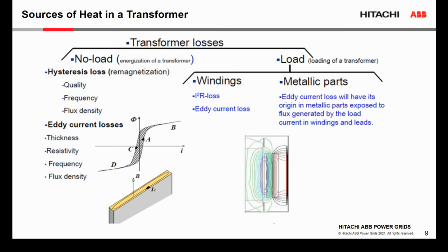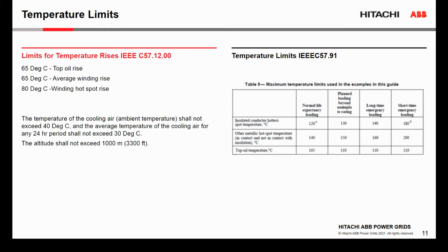To make sure that we won't reduce the life of the transformer, we have to maintain the temperature limits inside of the transformer. We have to control the temperature rises, because the temperature rises affect the life of the transformer, affect the mechanical strength of the insulation system, like paper or pressboard, and also another component of the insulation system, which is the oil.